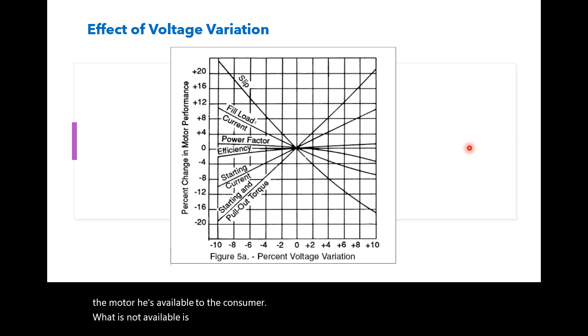So look at some of the parameters and what happens to them as we change the voltage. The starting and pull-out torque will reduce if the voltage at the motor terminal reduces, and increase when it increases. Similarly, the slip will increase when the voltage is reduced, but reduce when the voltage is increased. Full load current will go from one end to another end. The power factor will go from one end to another end. The efficiency is the only value which gets affected on either side of the extreme voltage variations.